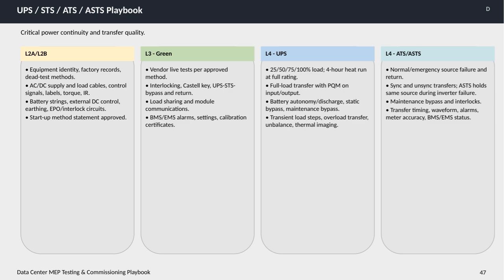At level 4 for the UPS itself, testing involves subjecting the system to loads at 25, 50, 75, and 100% capacity, followed by a 4-hour heat run at full rating to assess durability. Full load transfer tests are conducted with power quality monitoring on both input and output sides. Battery autonomy is checked through discharge testing, alongside static and maintenance bypass functionality. We also simulate transient load steps, overload transfers, unbalanced loads, and utilize thermal imaging to detect any hot spots or issues.